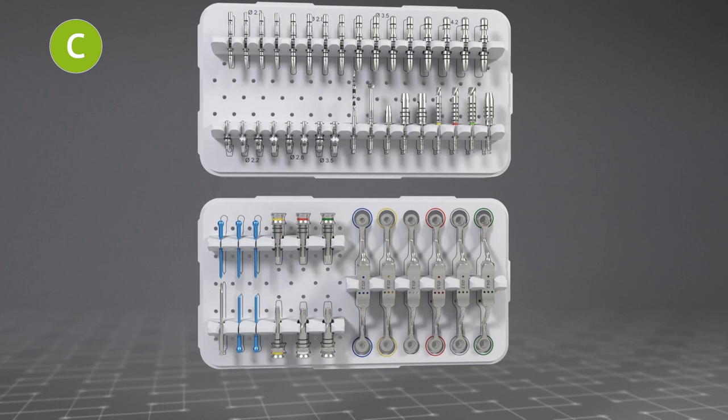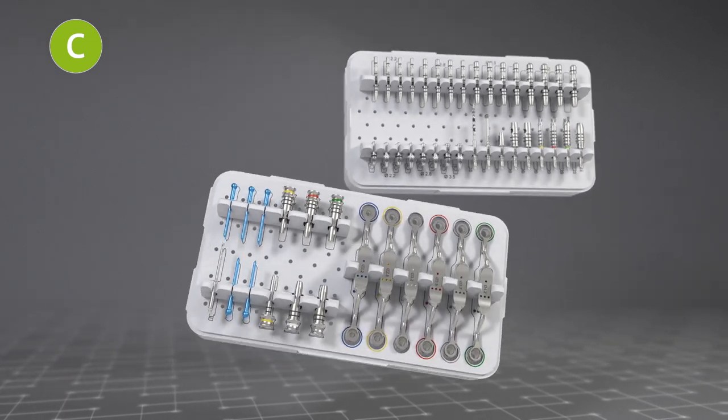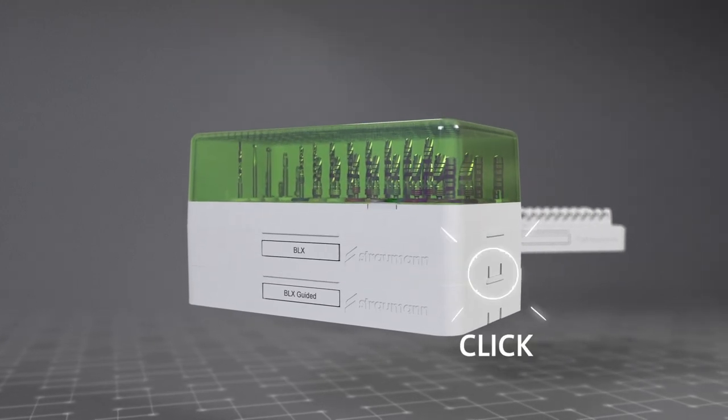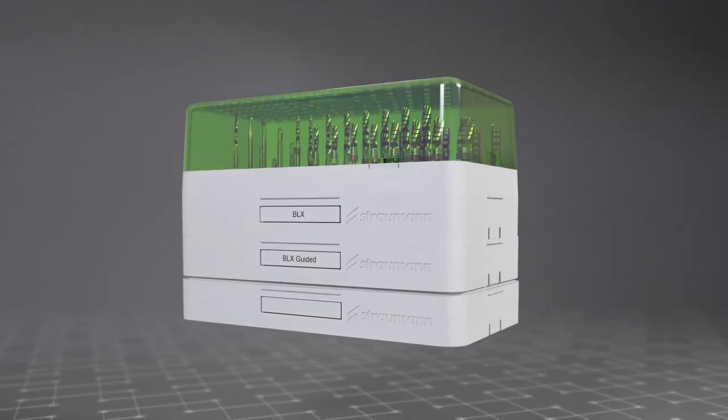Also, additional cutting tools with a dental coupling can be stored. The C modules can be autoclaved individually or stacked under the B module.